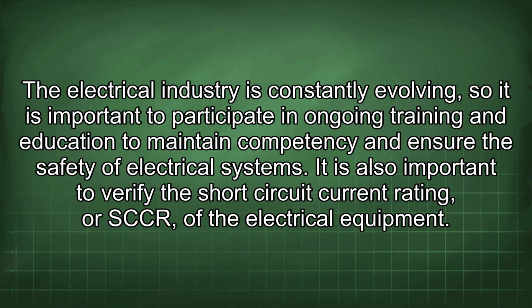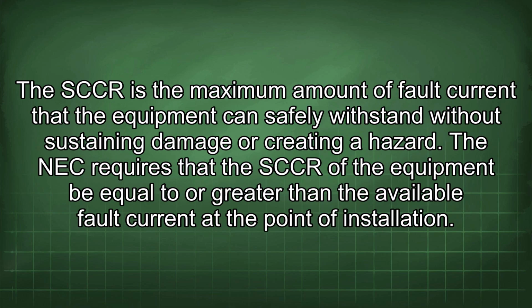It is also important to verify the short-circuit current rating, or SCCR, of the electrical equipment. The SCCR is the maximum amount of fault current that the equipment can safely withstand without sustaining damage or creating a hazard. The NEC requires that the SCCR of the equipment be equal to or greater than the available fault current at the point of installation.